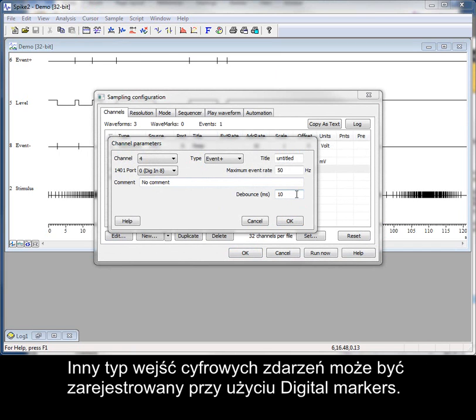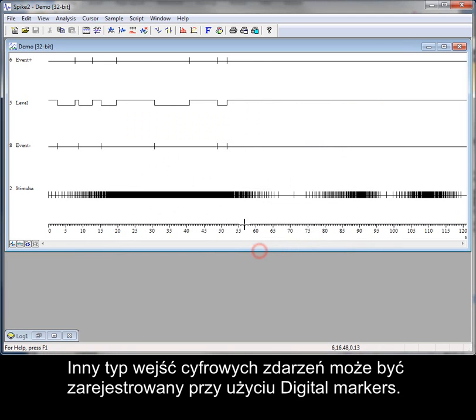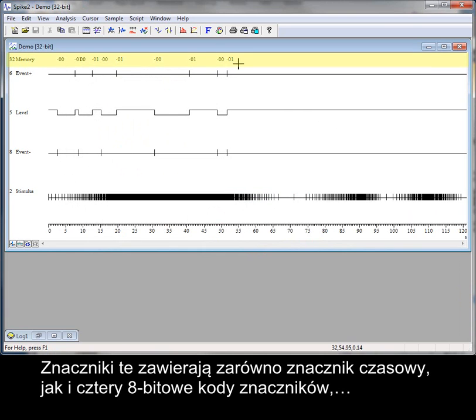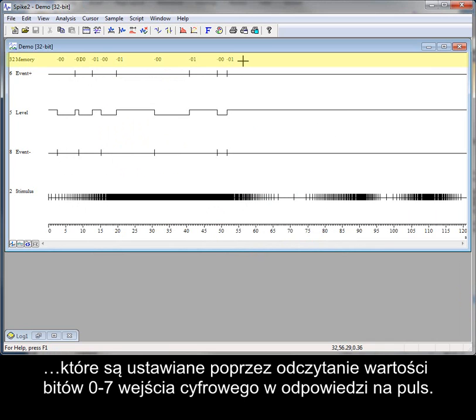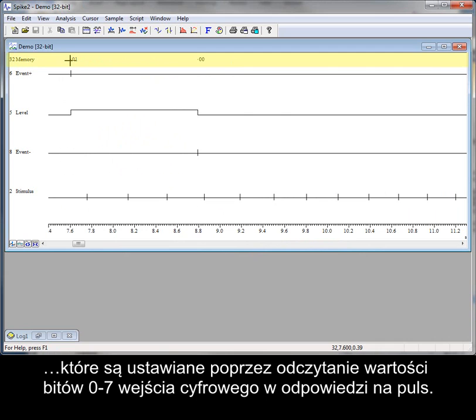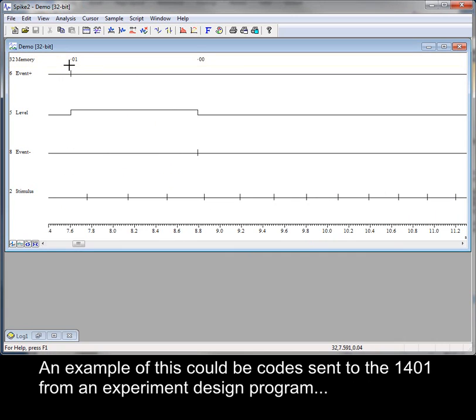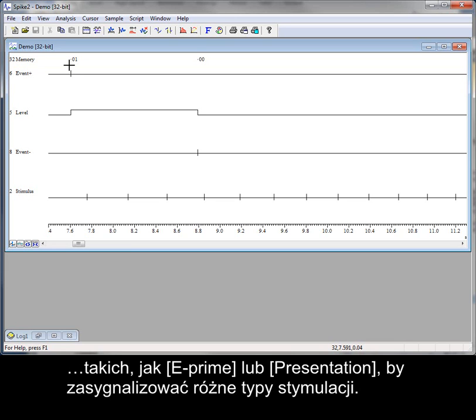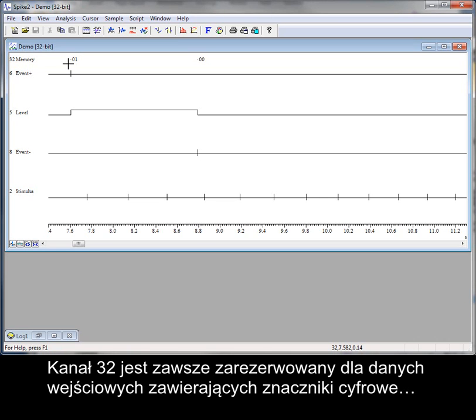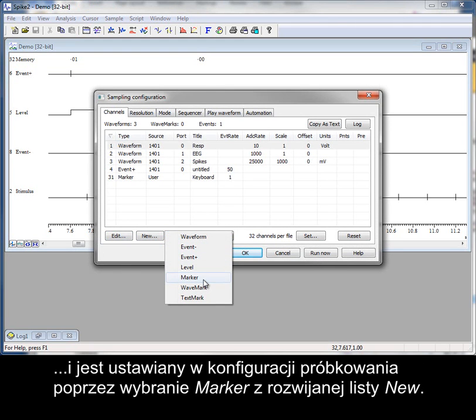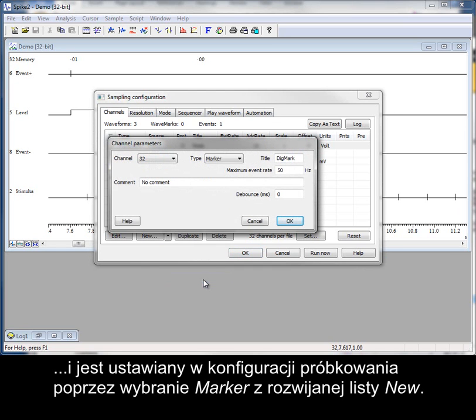Another type of digital input event can be recorded using digital markers. Markers contain both a timestamp and four 8-bit marker codes, which are set by reading the values of digital input bits 0 to 7 in response to a pulse. These marker codes are often used to signify certain experimental conditions — for example, codes sent to the 1401 from an experiment design program such as E-Prime or Presentation to signify different types of stimulus. Channel 32 is always reserved for digital marker data input, and is set up in the sampling configuration by selecting Marker from the New drop-down list.